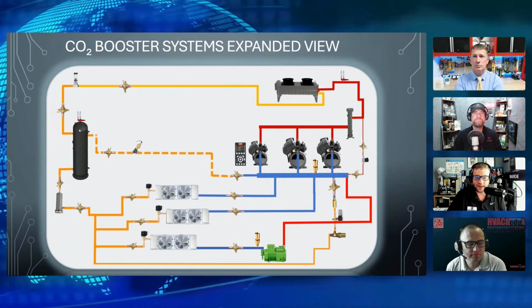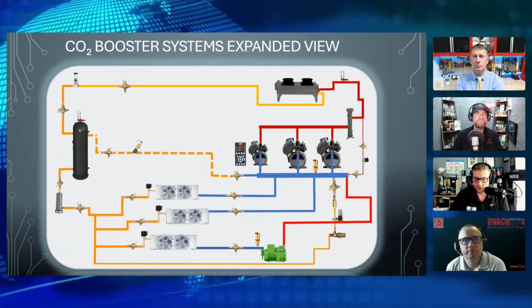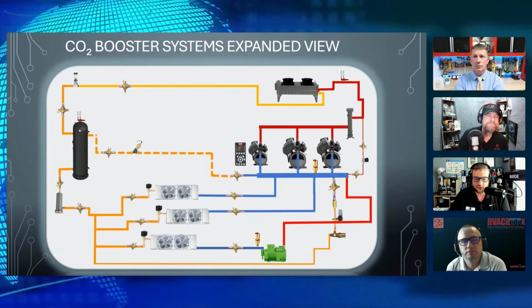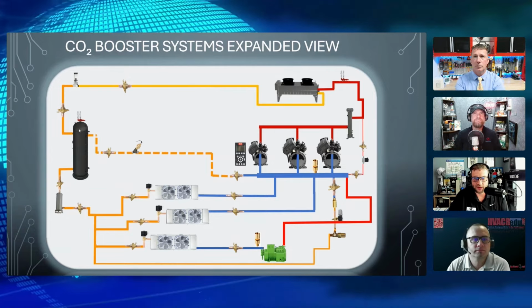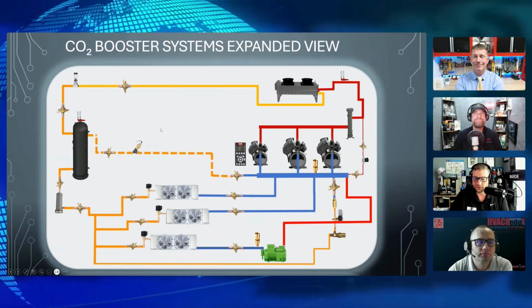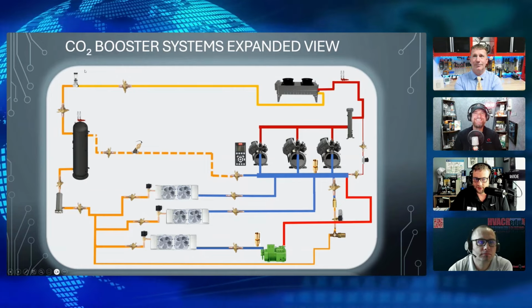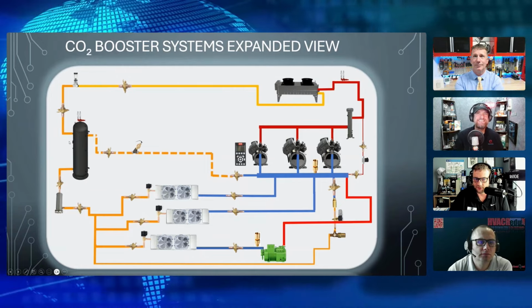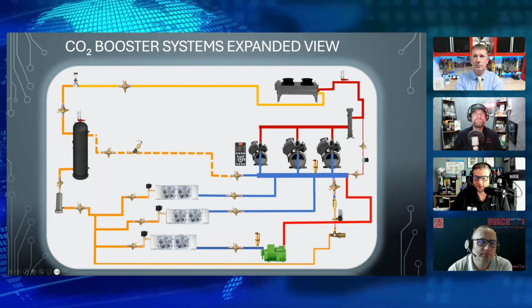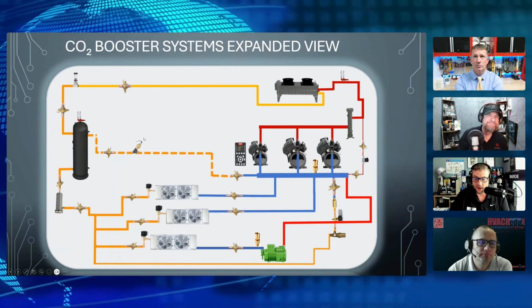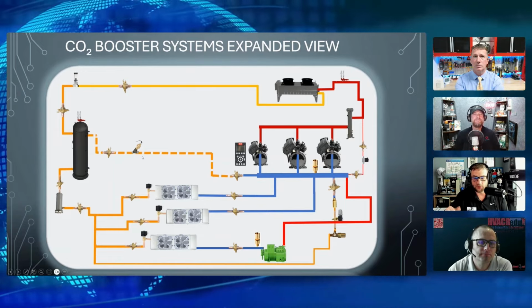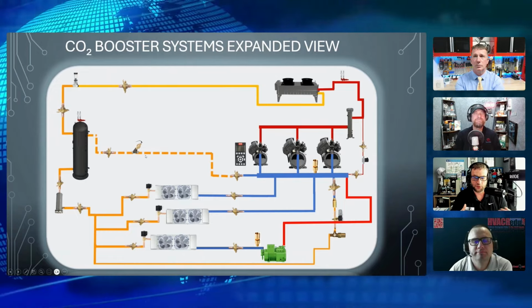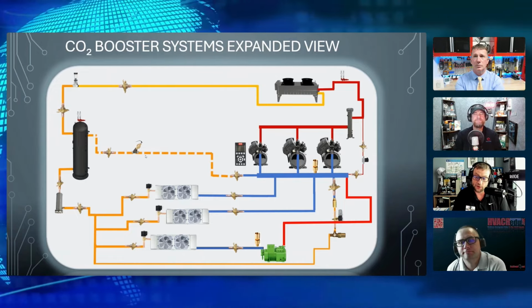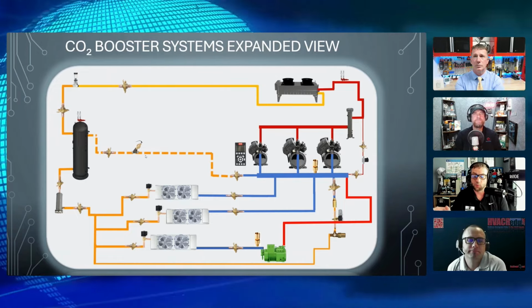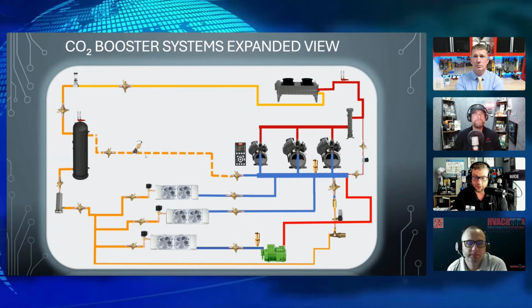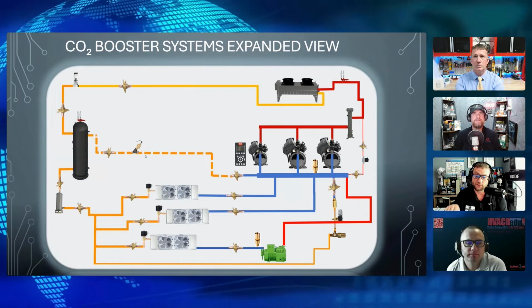Well, coming out of the dash line, which represents a little bit of liquid, a little bit of vapor, that's called the BGV, the bypass gas valve. That valve basically then feeds refrigerant down. Coming out of the receiver, the BGV, that's going to feed the excess vapor that's created. Because most of the time during subcritical operation, you'll typically maintain about 70% liquid and 30% vapor. When you run transcritical, you're only producing maybe 50% liquid and 50% vapor.